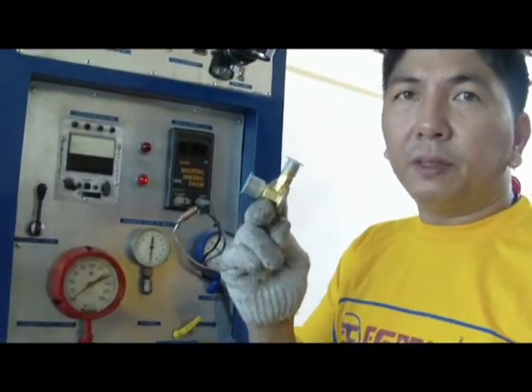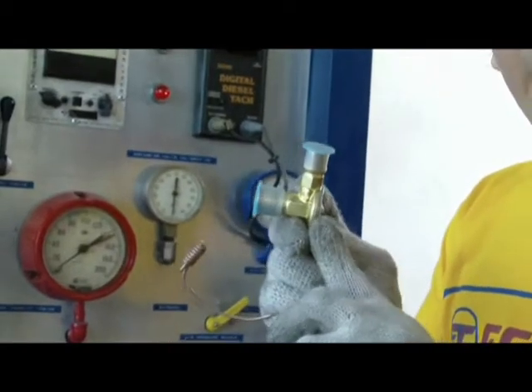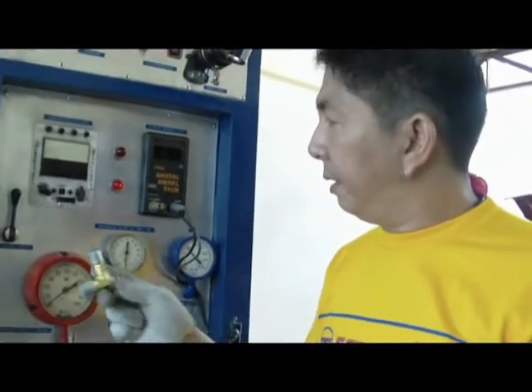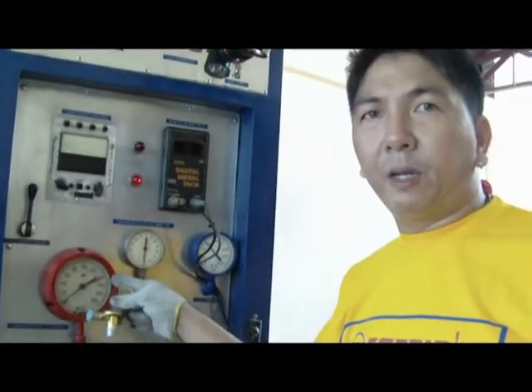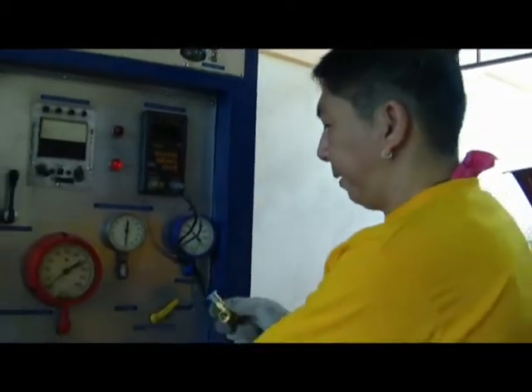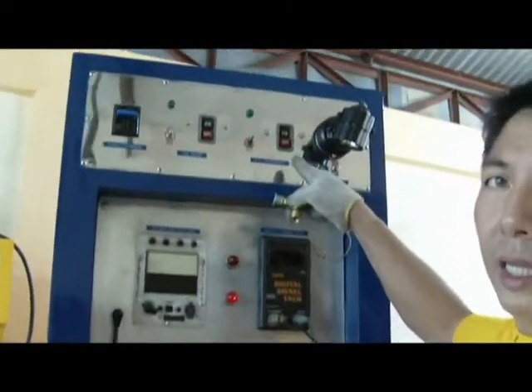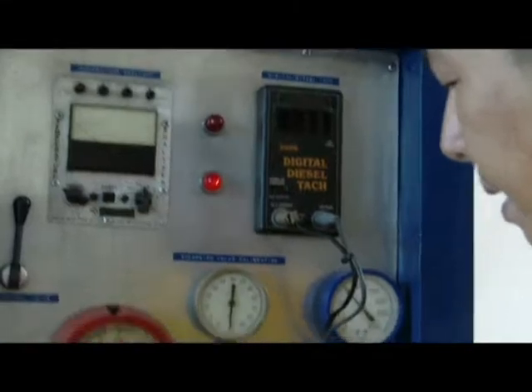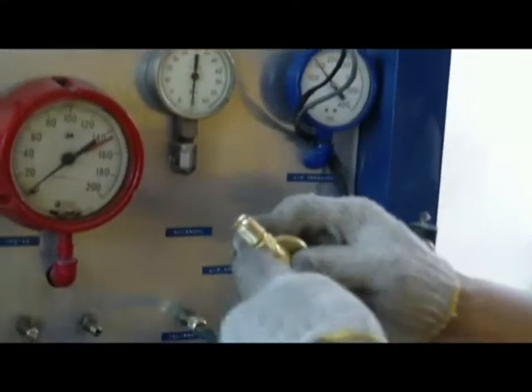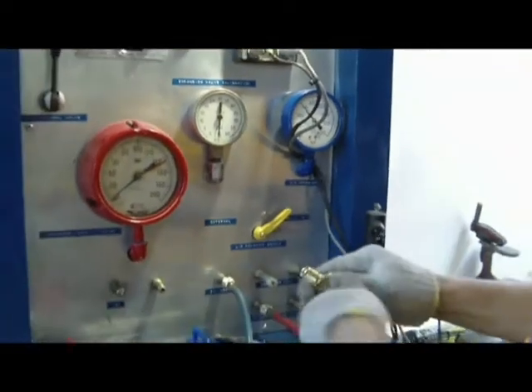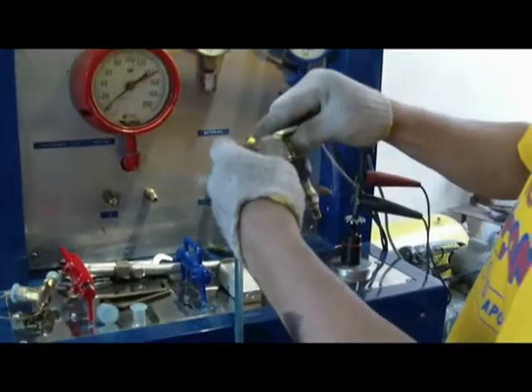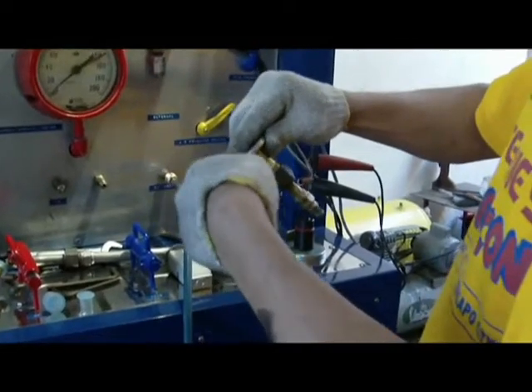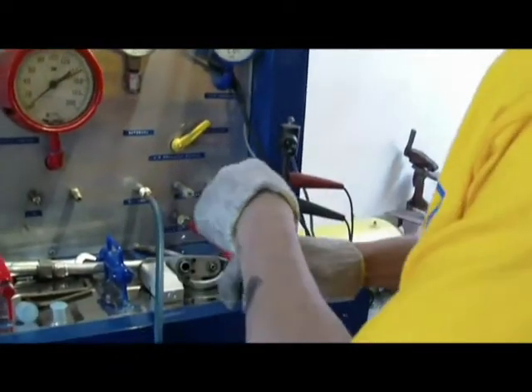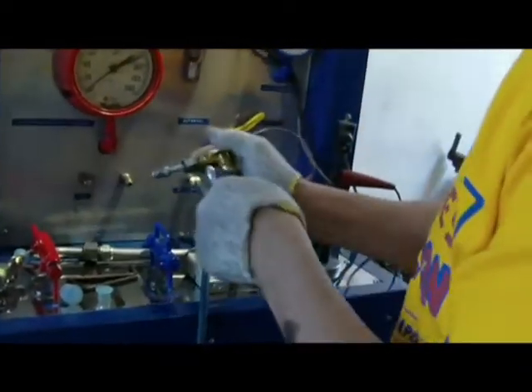This expansion valve should read around 18 to 20. It always depends on the capacity of the compressor. So I can calibrate it until 20, so it will match with the capacity of the compressor here. You see, it automatically shuts off the compressor. I just need to put adapter fittings here. This is the first step in the calibration. Need to tighten the fittings.